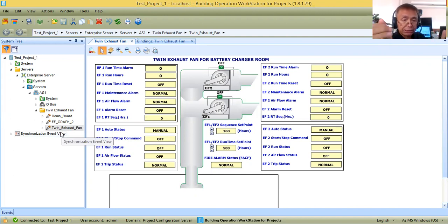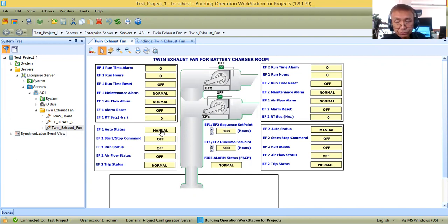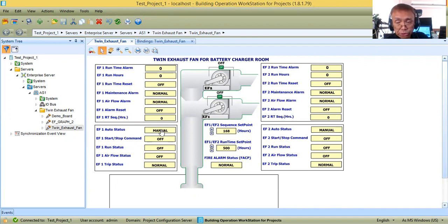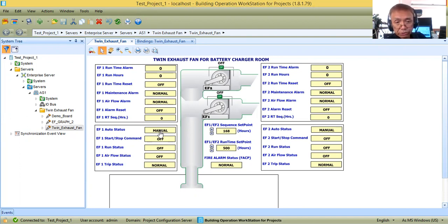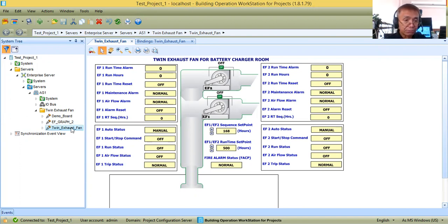When I say bind, you tell the BMS graphics where it will fetch the value. It will fetch the value from the IO module where we defined the point and where we pulled the cable from that IO module going to the actual selector switch in the motor control. When the selector switch is in automatic and the contact closes, that signal goes to the IO module, and the graphics will automatically display 'auto status'.